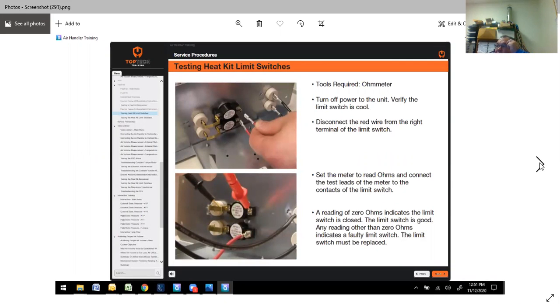If you're testing your heat limit switches, all you really need is an ohm meter. So if you look right here, this is 2 elements. You've got the beginning element on the left and the element on the right. So you can actually ohm from one side to the other. That will give you your ohm reading for the whole element. So if you're reading continuity all the way through that, you have a valid, complete element.